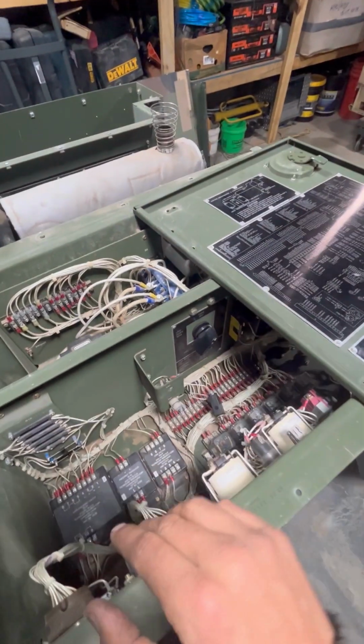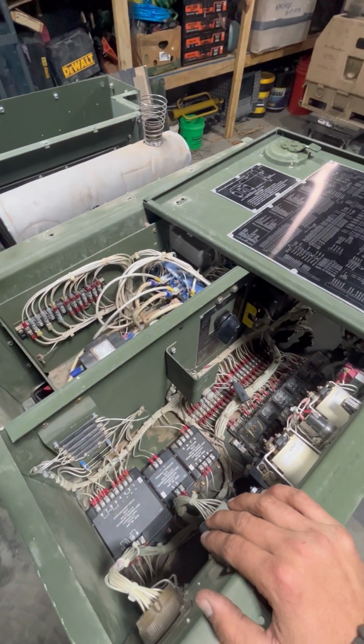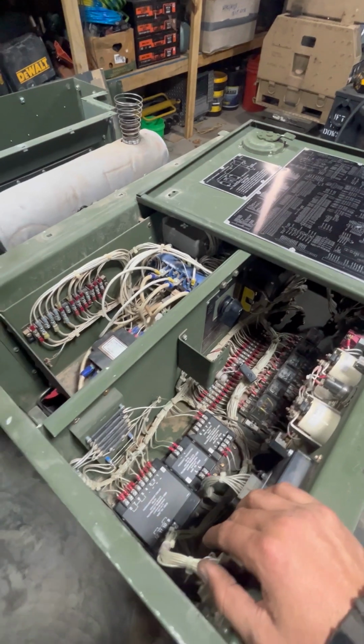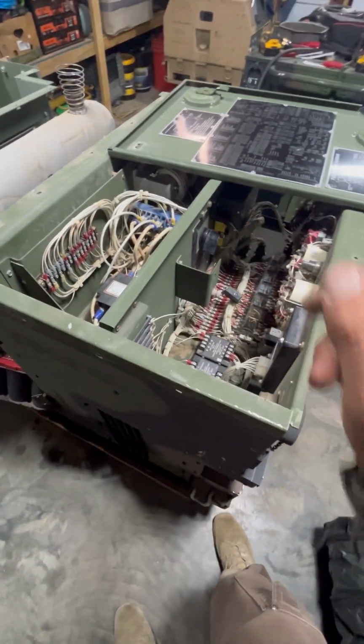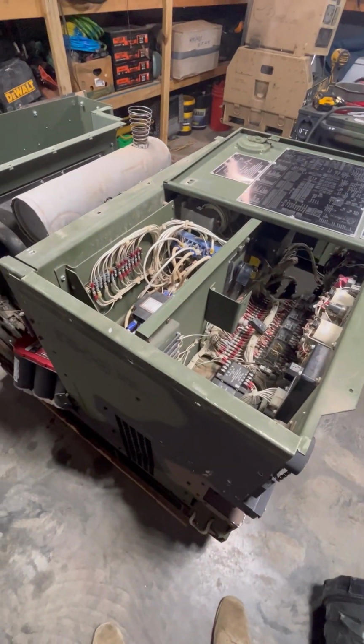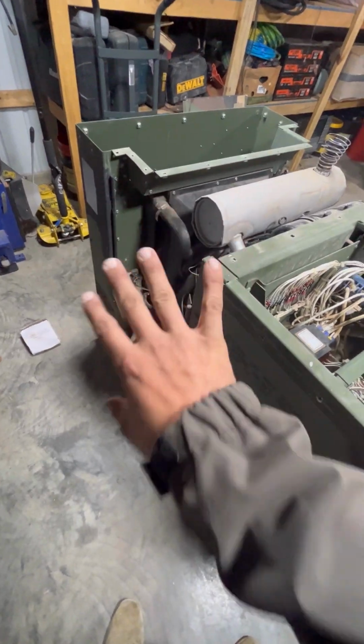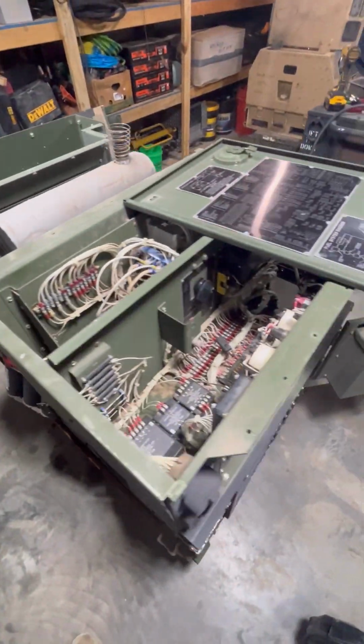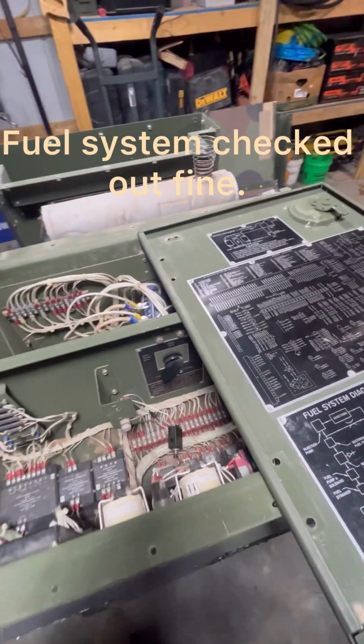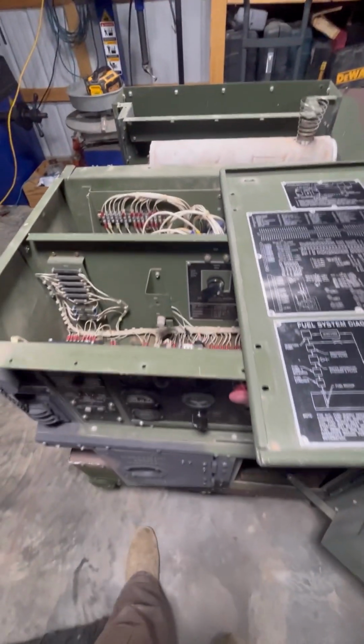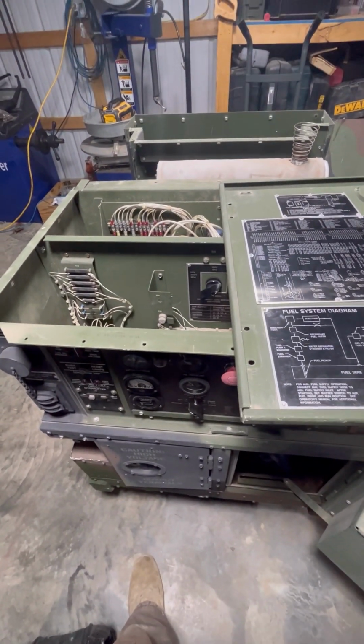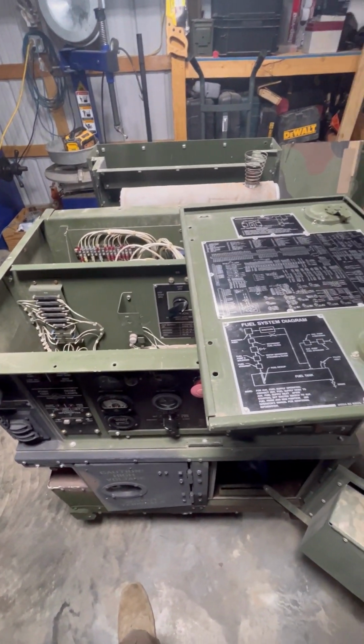Okay, so I took all the panels off. I checked for shorts, I checked for broken wires, rats' nests, anything I could think of to try to figure out why CB1 breaker is tripping. I checked, double checked, triple checked the fuel system. I even unplugged everything. And the thing that's interesting is the generator's only tripping CB1 when the generator's running.